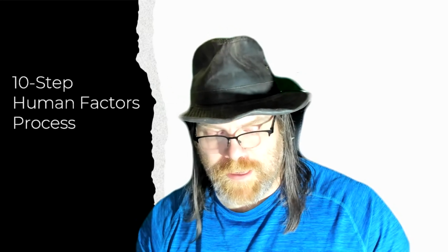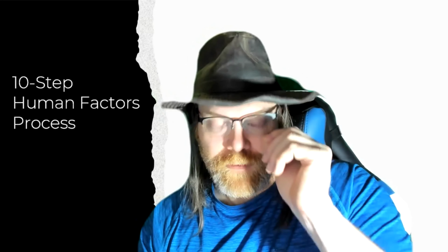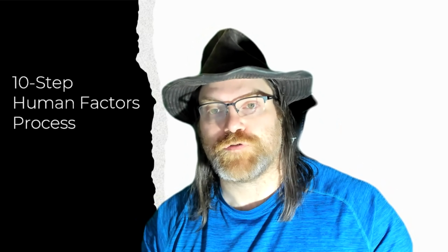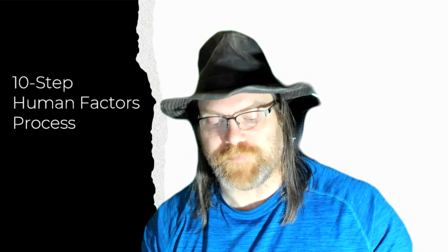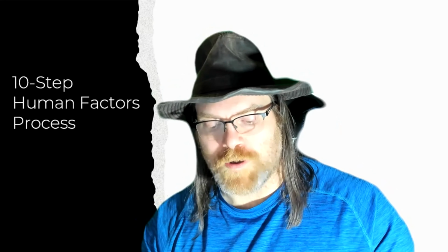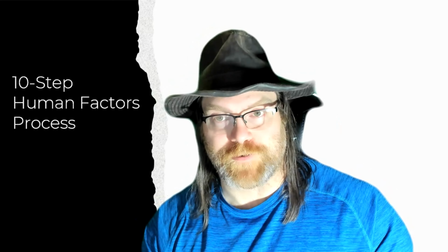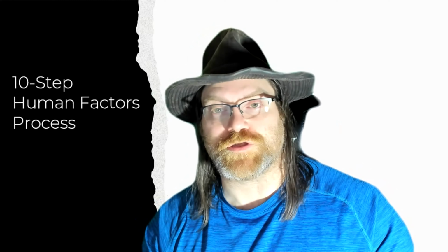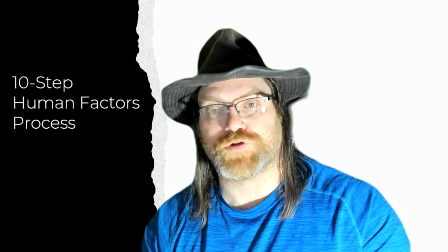Okay. Step 1 is definition. This relates to 3 different clauses in IEC 62366-1 2015. So I'm always going to give you the clause for each of these sections. You want to define what the indications for use are for your device. Number 2, who are the intended users? And you want to break that down into user groups.